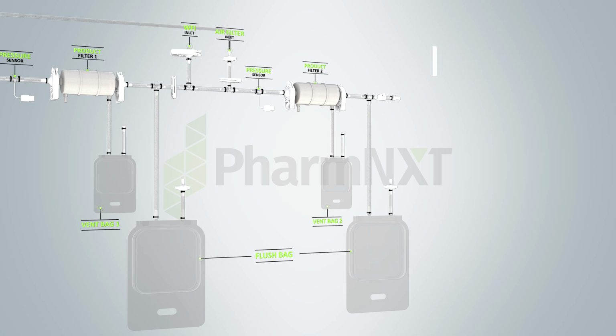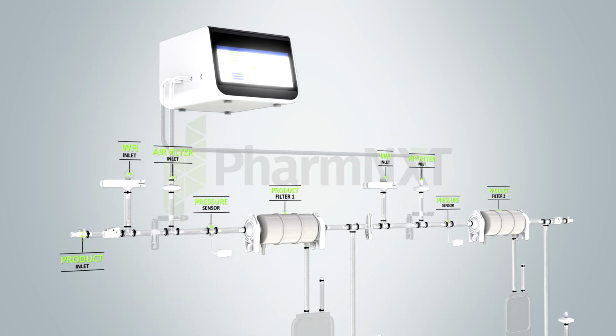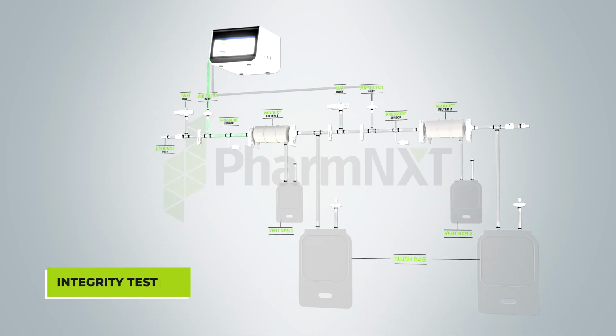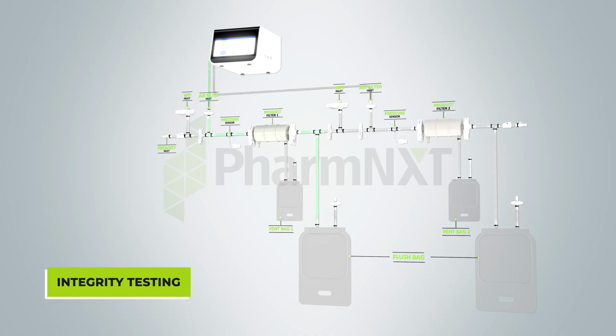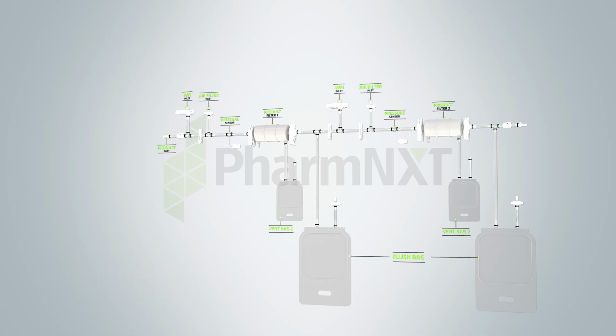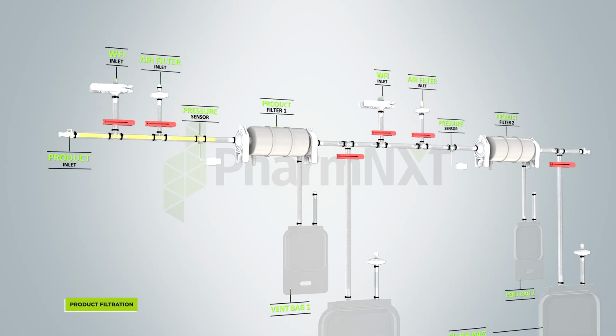After wetting, the assembly undergoes integrity testing. This critical step verifies the filter's performance and ensures that sterility standards are met. During testing, a compatible gas such as nitrogen or helium is introduced to check for any pressure differential that could indicate a filter breach. Our systems use high-precision integrity testers and are compatible with leading integrity test instruments, guaranteeing reliable results. Upon passing integrity testing, the system is ready for product filtration.